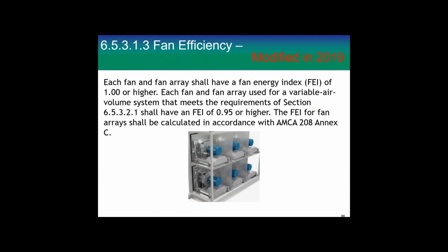So in 2019, we were looking at fan arrays because they're popular, and we said that it must have a fan FEI of 1 or higher. Each fan in a fan array that uses a variable air volume system, or a variable fan volume system, that meets the requirement of the sections on FEI shall be 0.95 or bigger. FEI shall be calculated in accordance with AMCA 208. So this is modified in 2019, as I told you. I'm trying to keep it to 16, 19, and 22. So you lost a little background here.